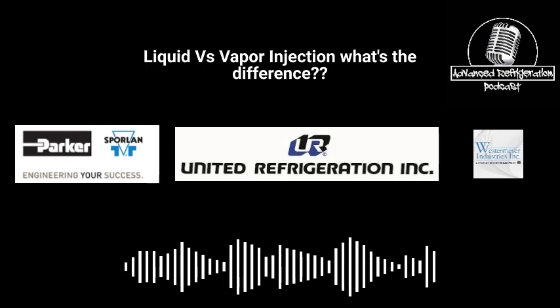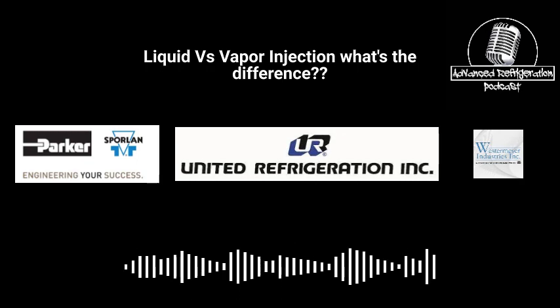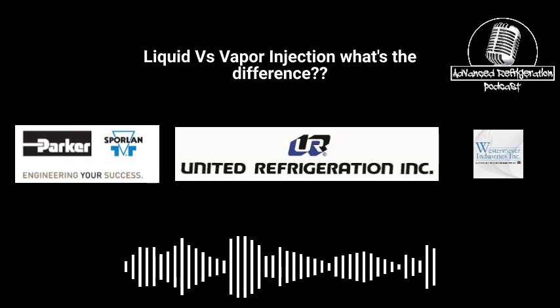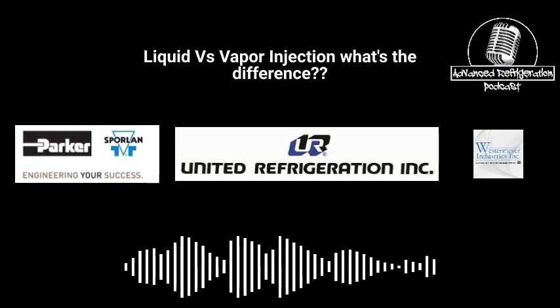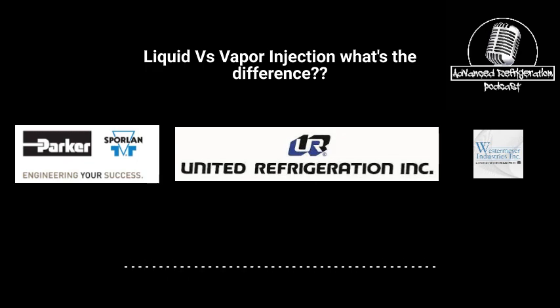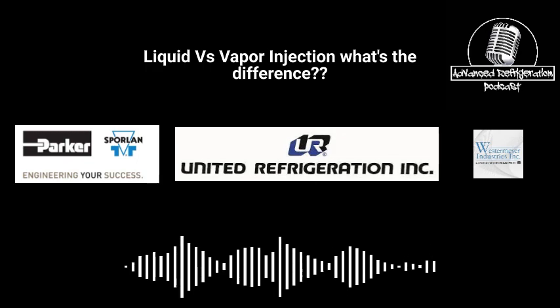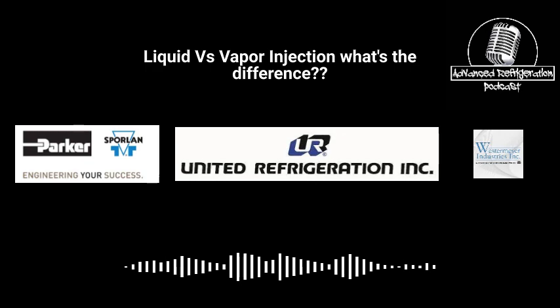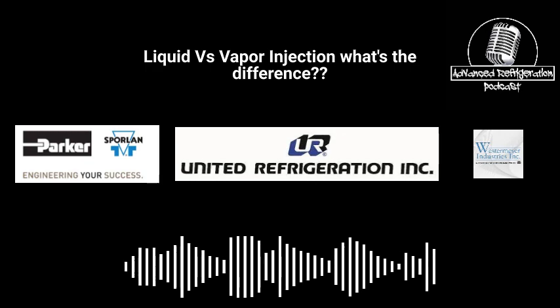Remember when they're not loaded 100%. When you have a rack manufacturer sizing everything for 100% runtime or load on that rack and they're only at like 70 or 80, you've got to remember your real load is probably closer to 50 most of the time. So that brazed plate heat exchanger has now become more efficient. In order to combat this from shutting on and off, you need to raise the EPR up, especially with blended refrigerants like 448.